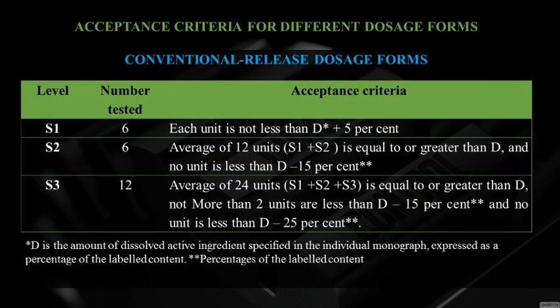Acceptance criteria for conventional dosage forms: D is the amount of dissolved active ingredient specified in the individual monograph, expressed as percentage of label content. Dissolution test is done using six units run for a specific period, then sampled and analyzed for dissolved amount. In the S1 stage, each unit must not be less than D plus 5% — every unit should be above 5% of the specified limit.